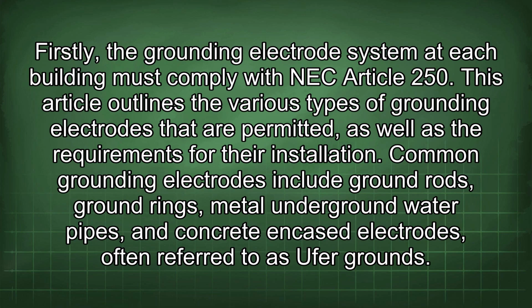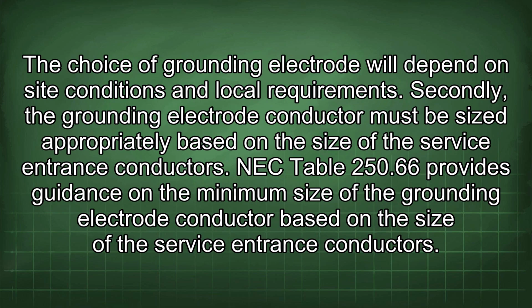Firstly, the grounding electrode system at each building must comply with NEC Article 250. This article outlines the various types of grounding electrodes that are permitted, as well as the requirements for their installation. Common grounding electrodes include ground rods, ground rings, metal underground water pipes, and concrete encased electrodes, often referred to as Ufer grounds. The choice of grounding electrode will depend on site conditions and local requirements.